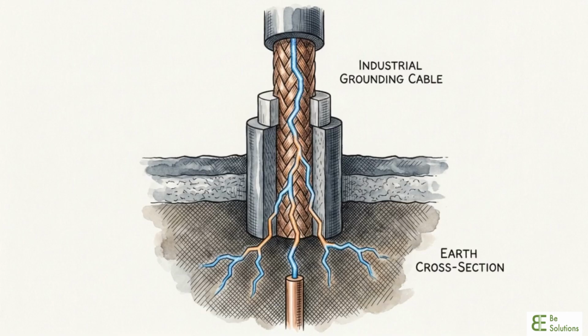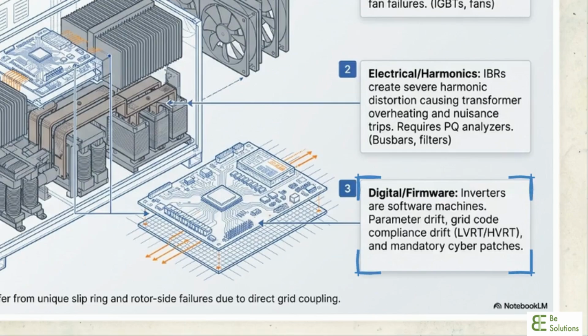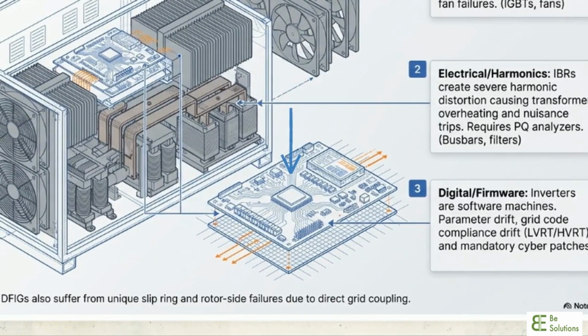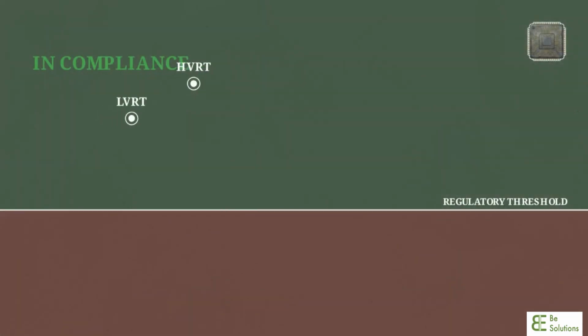Once identified, physical filters are deployed to block these high-frequency currents or provide a safe, low-impedance path to shunt them harmlessly to ground. Yet the most insidious vulnerability isn't physical at all. It resides in the programming. Because an inverter responds to grid faults using synthetic firmware rather than physical momentum, those programmed responses can shift over time. Essential algorithms dictating low-voltage ride-through and high-voltage ride-through protocols can suffer from parameter drift, pushing the asset out of alignment with strict regulatory standards.